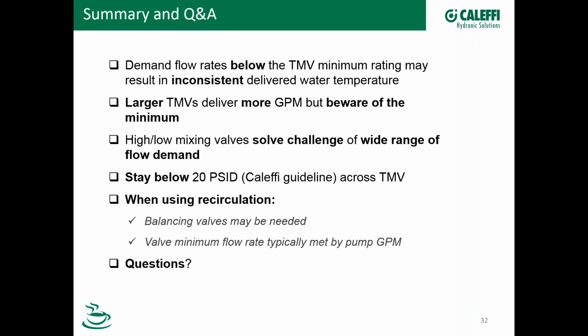One thing I'd like to add too, Cody, is sometimes you get the call and the symptom is that our valves are hunting all over, the temperature is inconsistent or thready, it's warm, it's hot, it's cold. These valves, when you put them in systems that have hard water, do scale up from time to time, and you may need to take them apart and delime them, or soak them in some vinegar, or run a delimer through it. It can be the same symptom presentation where you think the valve is bad or it's a recirc issue, and it could be the valve is just sticking up in there from minerals in the water.